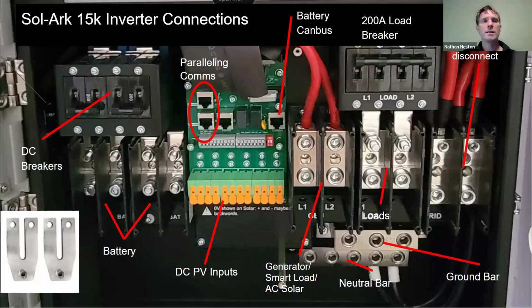Let's look at the inputs of a Sol-Ark 15K. And I've taken a picture of a Sol-Ark 15K from our office down in Oxnard and just pointing out a couple of things to you. So first, on the left side of the inverter, these are your battery inputs. And it's broken up into 2 200 amp breakers. And Sol-Ark did this so that you could connect your battery bank to the inverter with 2-aught cabling.